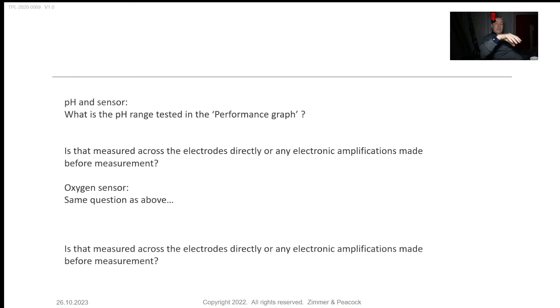Just looking at the pH sensor, there is a data sheet there. Along the top of the data sheets, I've zoomed in here. I can see that this data was gathered at 7.4, this data was gathered at 3.6, this data was gathered at 9.9, and so on. So the quick answer to your question is this is the range that we tested at when making that data sheet. It doesn't mean it's the ultimate range. I've seen some data in this presentation today where we often test between pH 2 and pH 10. So we almost went to pH 2, but we only went to 3.6 when making that particular data sheet.